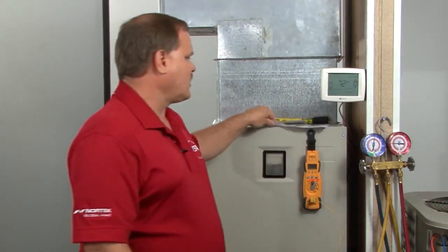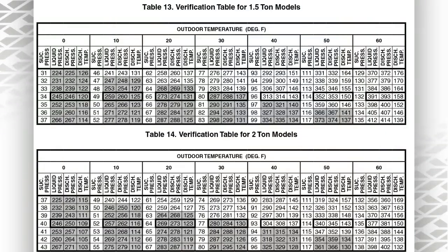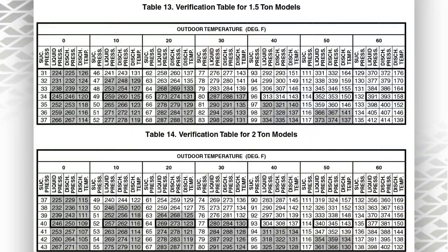All right, so now we'll talk about the charge for heating mode. So with the FT4BE heat pump, this is referencing your outdoor temperature. It's going to reference your suction pressure, your liquid pressure, your discharge pressure, and your discharge temperature. So, as I said before, when I was pointing at the service valves, unless you put a Schrader core up ahead on that line, you can't get the liquid pressure. But you don't necessarily need to. You get the discharge pressure. That's going to be off your gauge. You can get your suction pressure, and you can get your discharge temperature. That discharge temperature is the one that I want you to focus on.